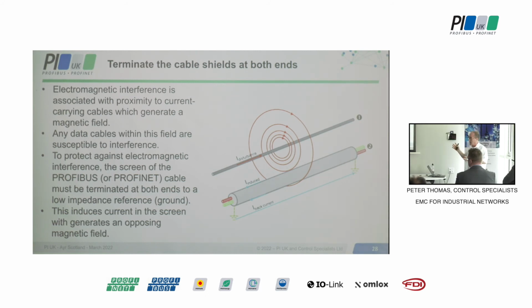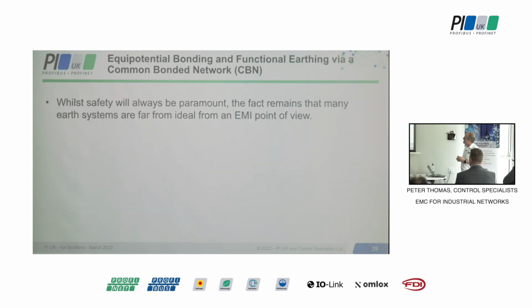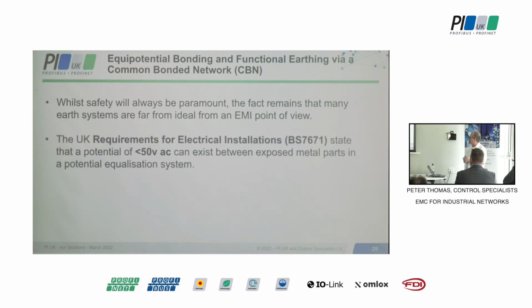That's what we would like to do. So by definition, if you only ground at one end, then you have no protection against magnetic coupling. But if you haven't got a source of magnetic coupling, it's not a problem anyway. Now, safety is clearly paramount here, and the problem is that the bonding infrastructure that we have, whilst it might be electrically safe, it's far from ideal when we come to electromagnetic interference.